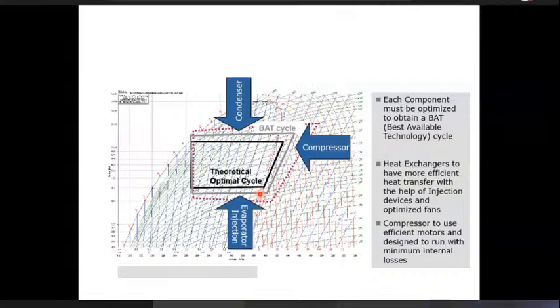The compressor motor would have rejected some additional heat at this point. So this point would move towards the right from the ideal theoretical cycle, because of the heat addition. Whereas in a scroll or a reciprocating compressor, the heat addition to cool the motor is happening right here. So this would be a little more severe penalty on the coefficient of performance, but it is always accepted because of the reliability impact that it has.